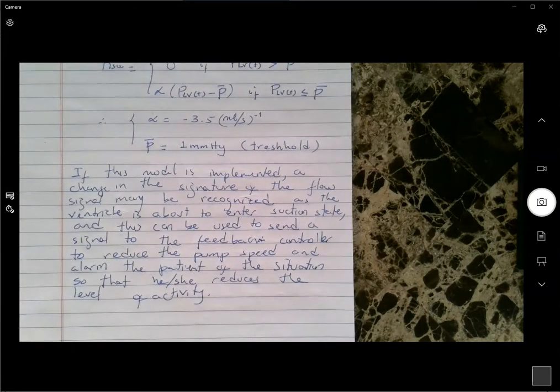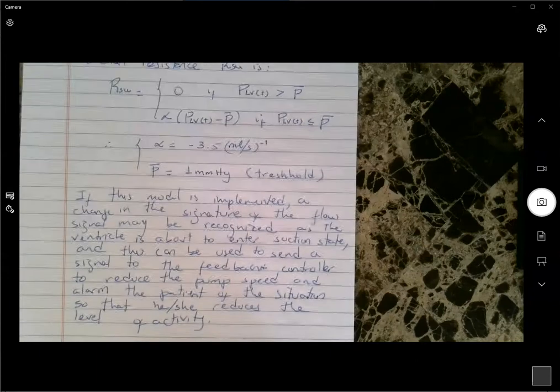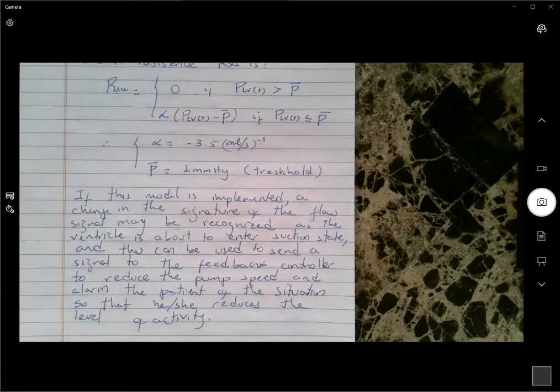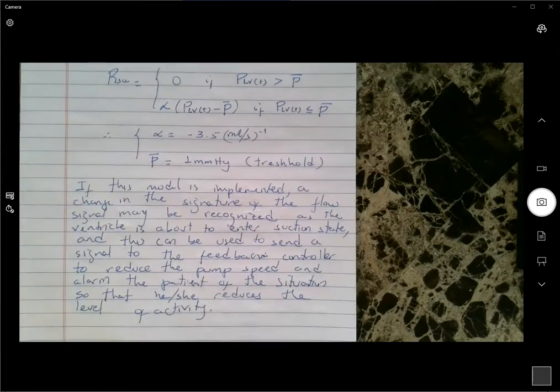So this is actually a very simple way of determining this. You can use a not very sophisticated pattern recognition, so machine learning, to look at the pump signal, the pump flow signal. Again, the only thing we can measure from the system directly is probably the pump speed. There's no way we can implement a flow sensor directly in situ inside the patient, or even a pressure sensor—nothing that interrupts the flow itself.